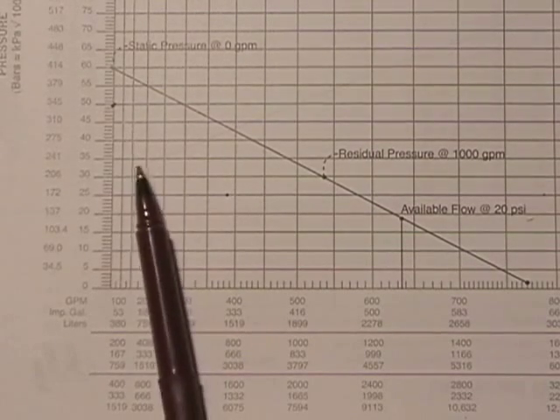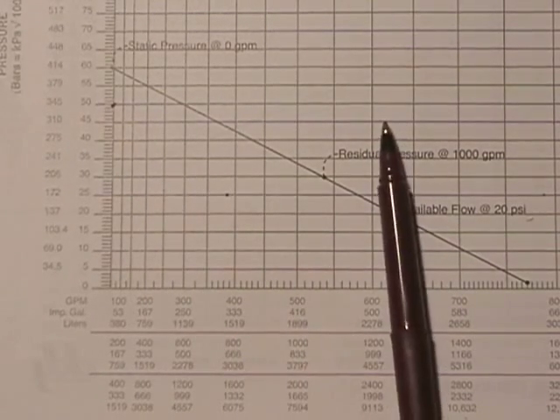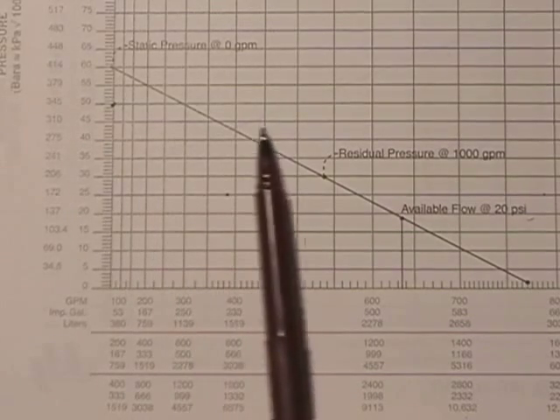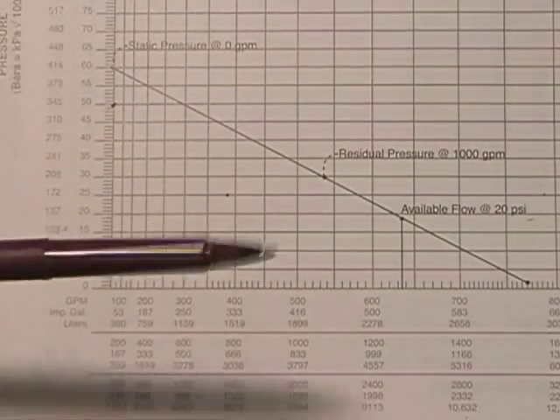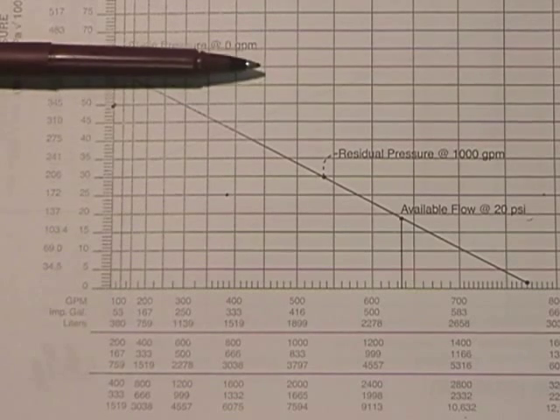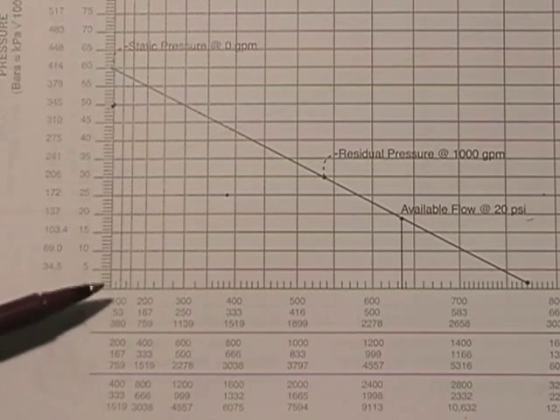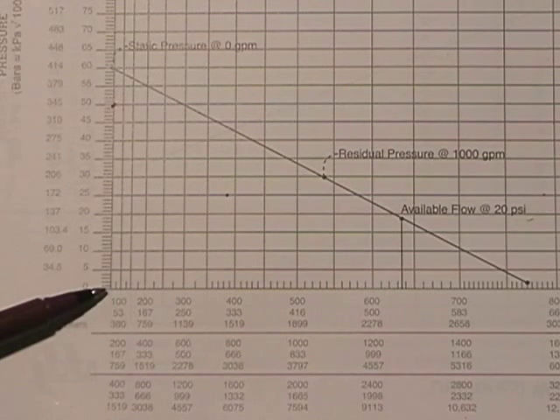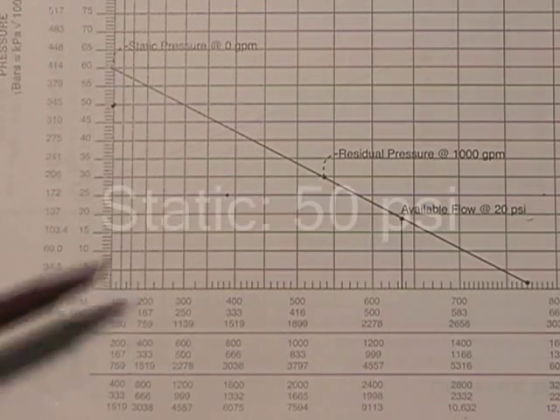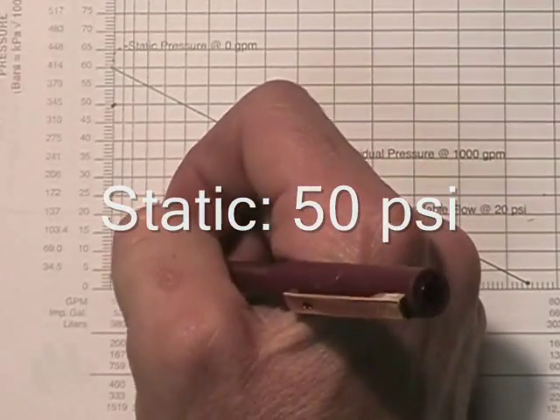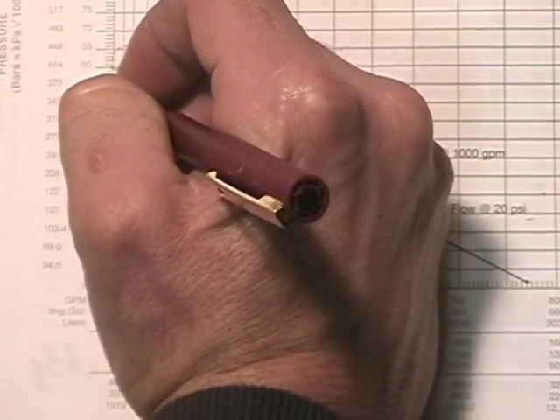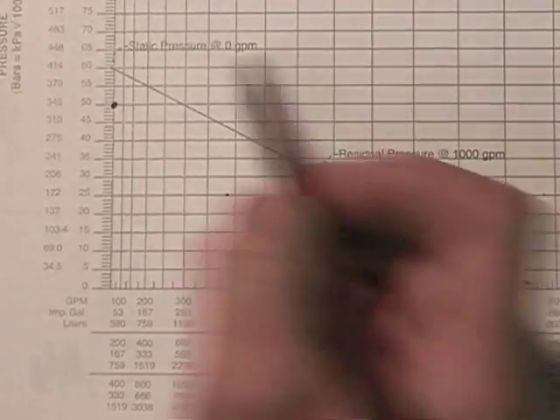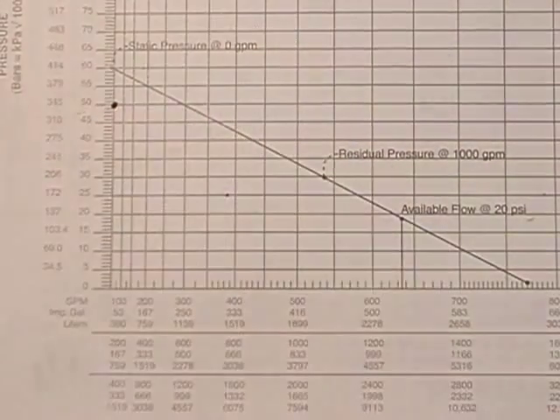We're going to take a chart here. From left to right, the chart is listed in gallons per minute, and from bottom to top are our pressures. Since the very corner here is zero pressure, 0 gallons per minute, we're going to put in our static pressure. Let's say the results of our test say we started off with a static PSI of 50. So we follow the line up at 0 gallons per minute and put a dot right at 50 PSI. So we're at 50 PSI for our static.